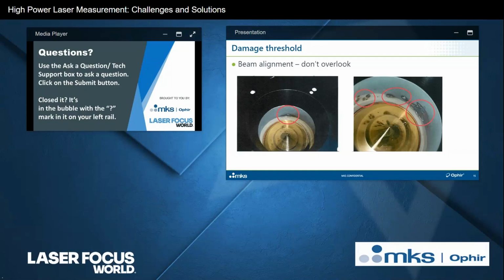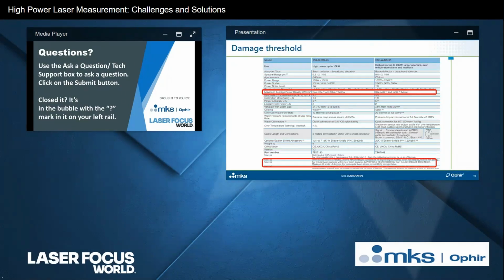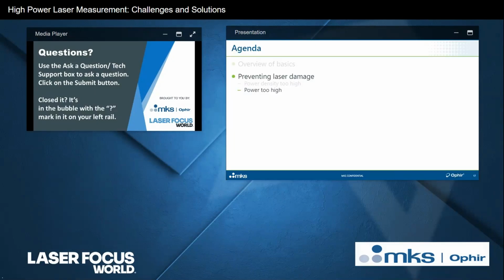This is actually expressed in Ophir's data sheets. Here you can just see an example. I don't know if you can read what it says there, but we mention here that the damage threshold that we specified there assumes a circular beam that's centered on the middle of the aperture on the cone. It has to be centered to within plus minus whatever. I also can't read what it says here, but you get the idea. So that's something that we do point out actually in block letters in the data sheet. So that's preventing laser damage due to power density being too high.